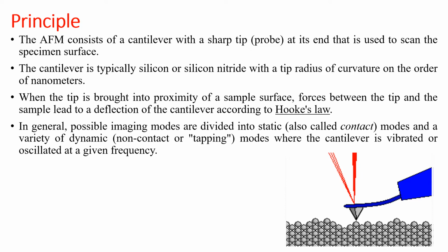object on the screen. Basically, it consists of a cantilever which is made of silicon or silicon nitride with a tip radius on the order of nanometers. When this tip is brought in contact with the sample surface, the forces between the tip and the sample lead to deflection, which is according to Hooke's law. And second, this deflection is also because of the van der Waals forces.